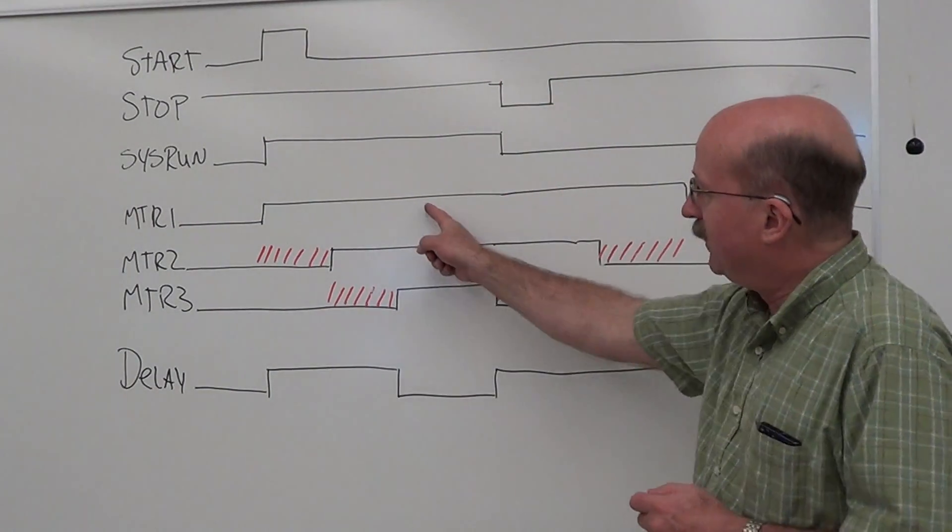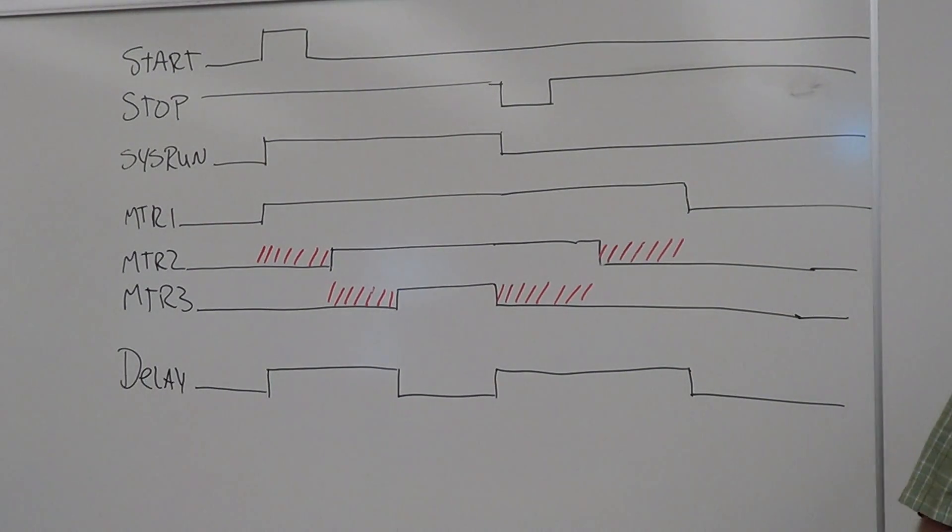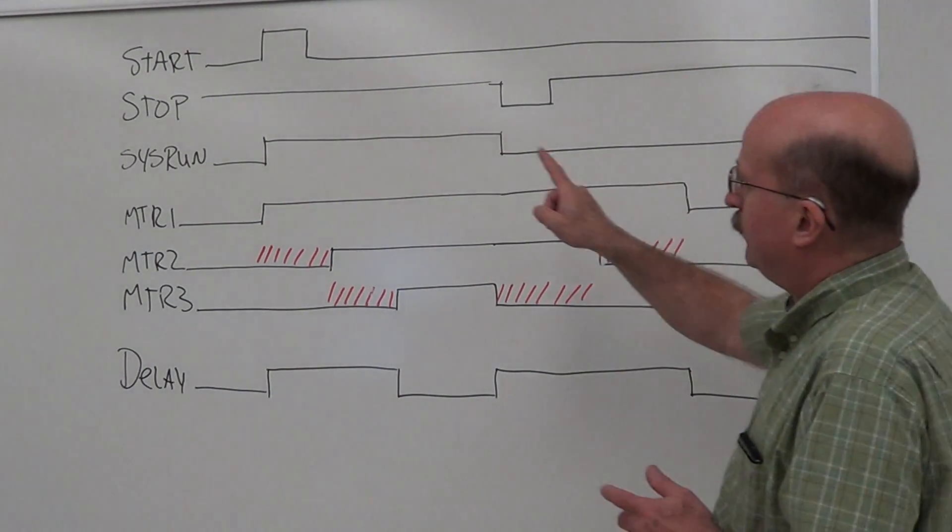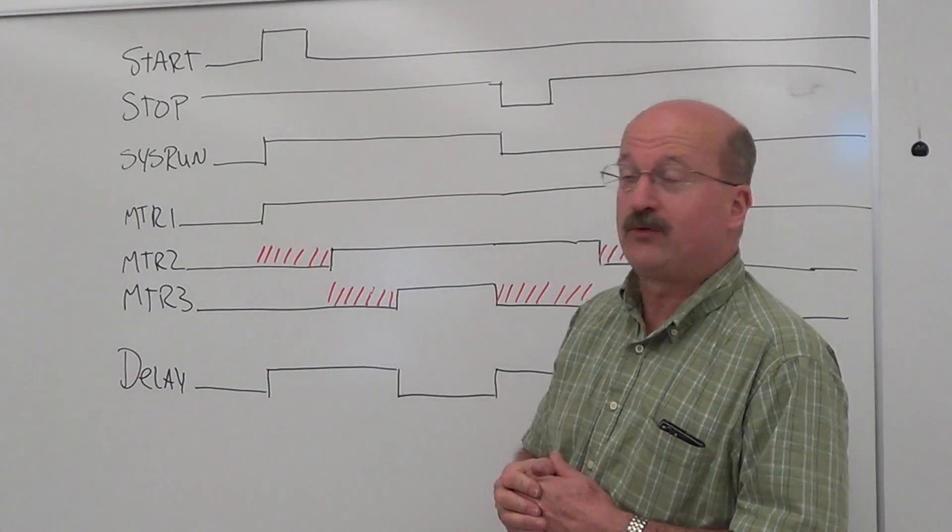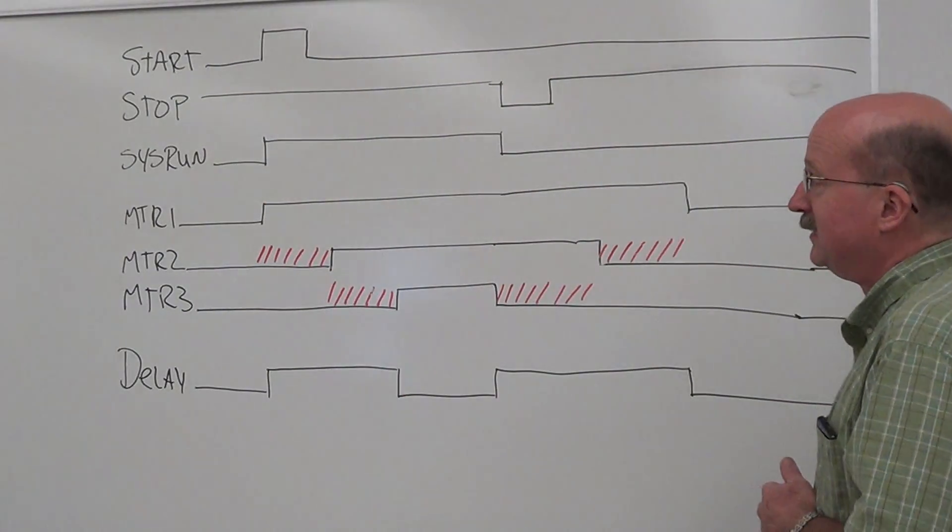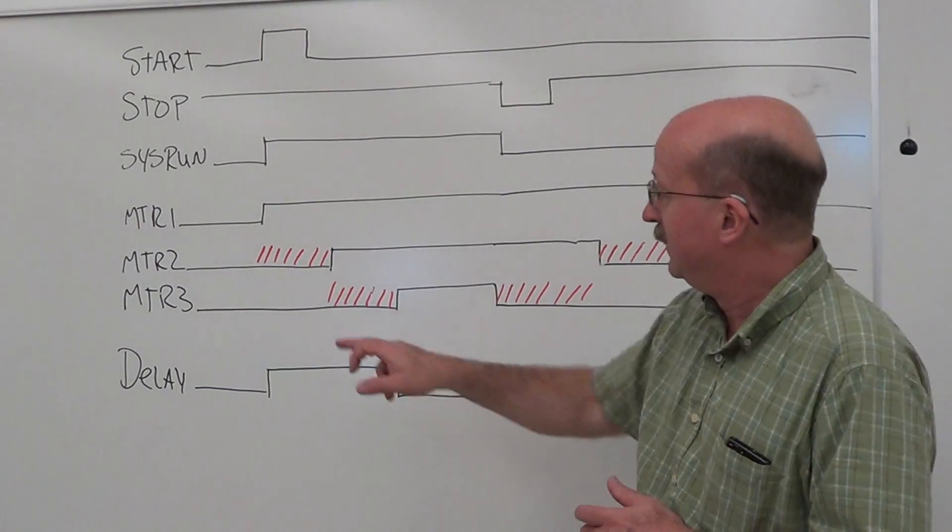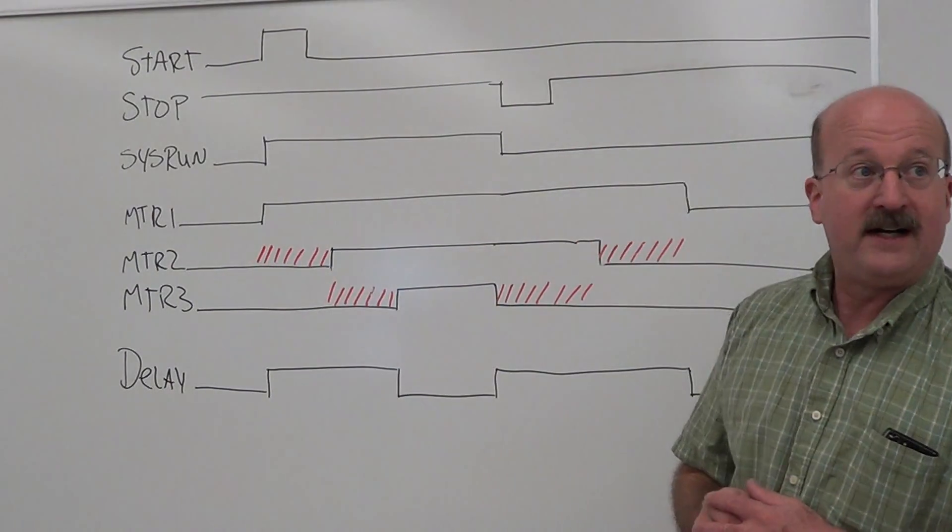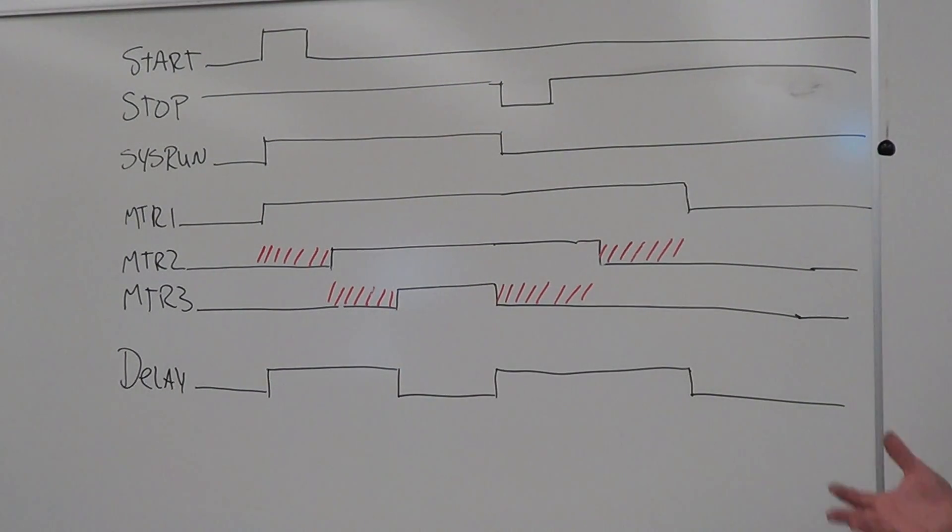We've got our start button and our stop button, we've got our three motors, and you have your delay indicator. So push the start button. We have our internal coil sys run which turns high and starts the whole sequence. Motor one turns on immediately.